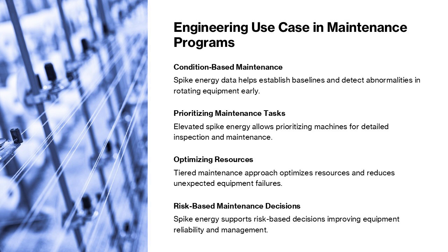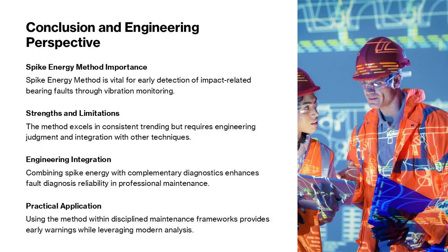Machines exhibiting elevated or increasing spike energy can then be prioritized for detailed analysis. This tiered approach optimizes resources and reduces the likelihood of unexpected failures. From an engineering management perspective, spike energy supports risk-based maintenance decisions and contributes to improved equipment reliability. In conclusion, the spike energy method remains an important part of the historical and practical foundation of vibration-based condition monitoring.